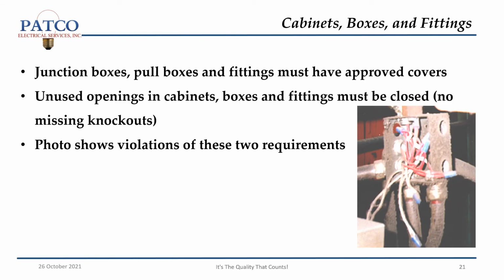Cabinets, boxes, and fittings. Junction boxes, pull boxes, and fittings must have approved covers. Unused openings in cabinets, boxes, and fittings must be closed. No missing knockouts. The photo shows violations of these two requirements. Of course, it doesn't have a cover, and there are knockouts missing.